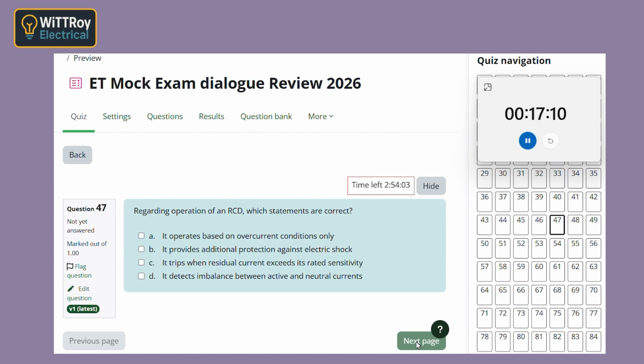Exactly. Now, the wrong one says it operates based on overcurrent only. That is wrong because an RCD is not an overcurrent device. It does not measure total load current in the same way a fuse or circuit breaker does. It measures imbalance. So if I have a perfectly balanced heavy load, an RCD might not trip at all. Correct. Heavy load alone does not make an RCD trip unless there is imbalance.